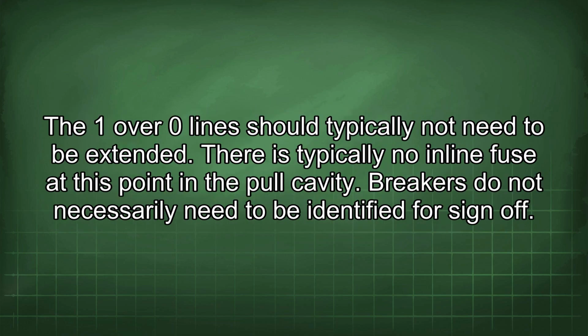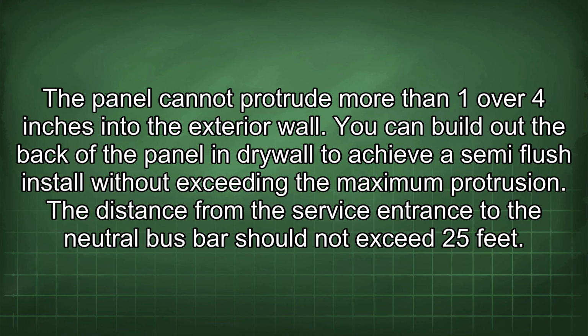The 1/0 lines should typically not need to be extended. There is typically no inline fuse at this point in the pull cavity. Breakers do not necessarily need to be identified for sign-off. The panel cannot protrude more than 1/4 inches into the exterior wall.